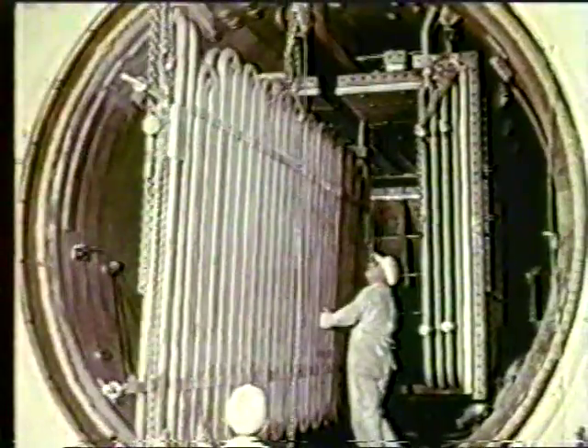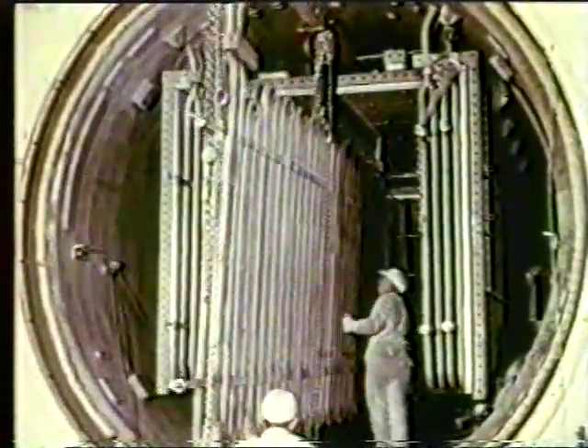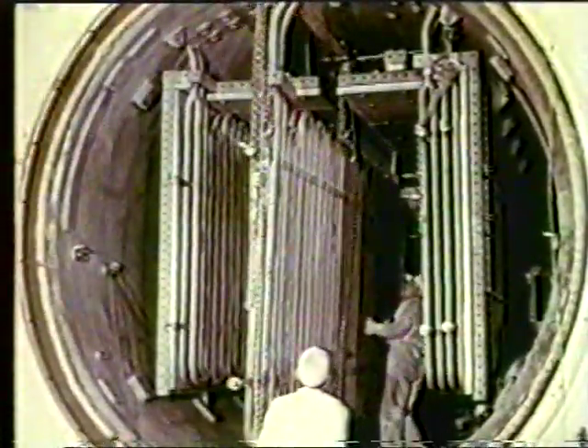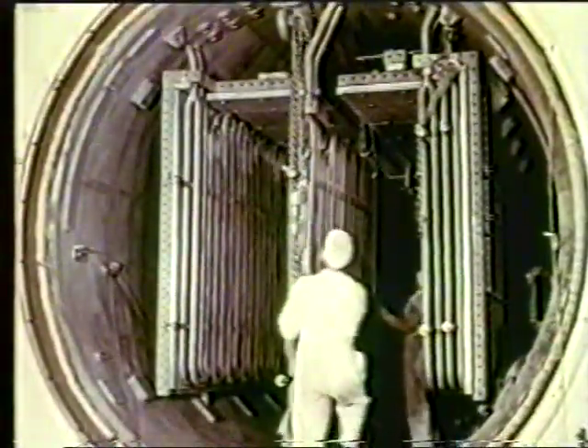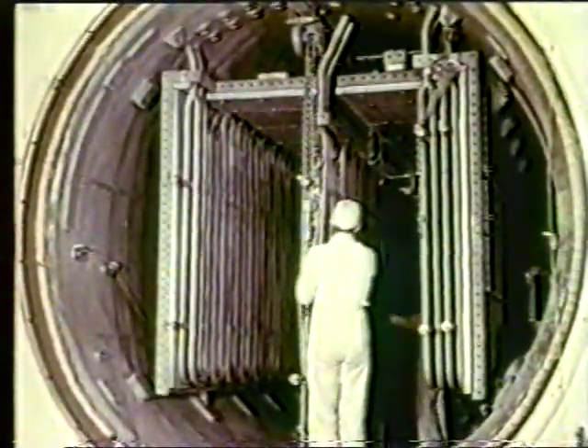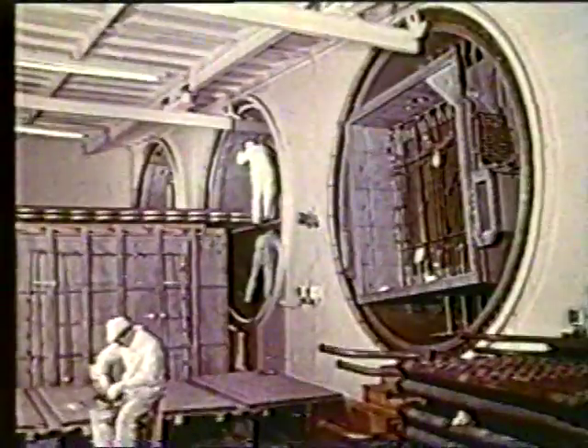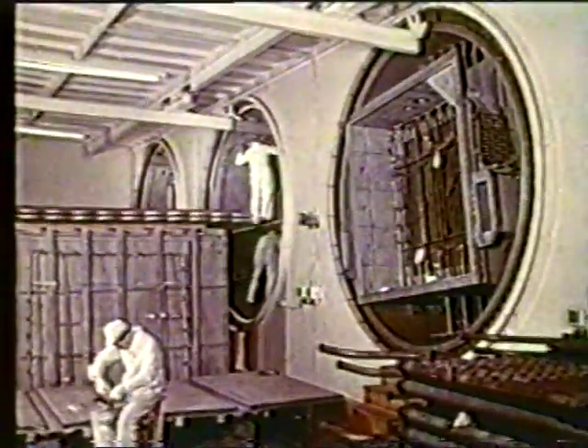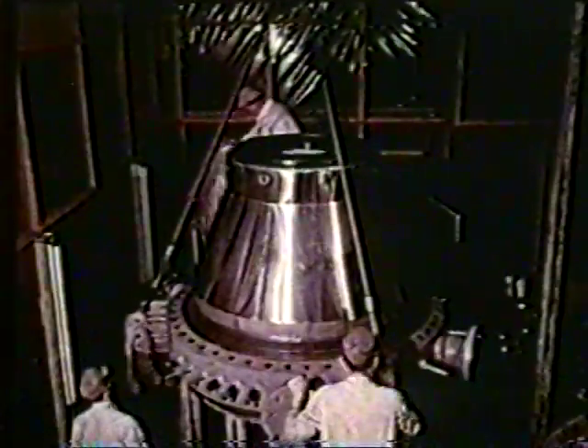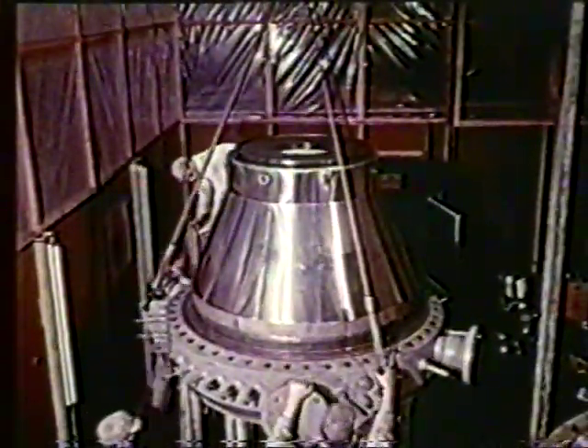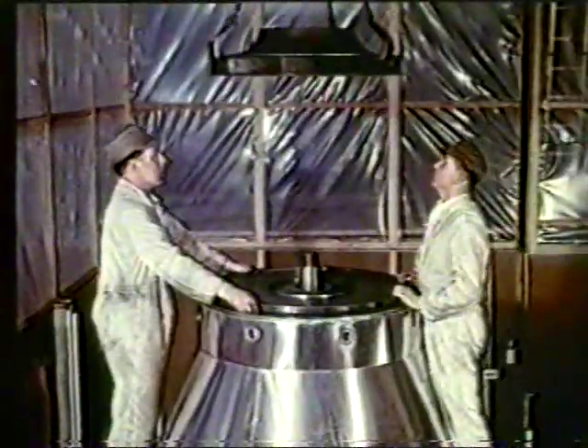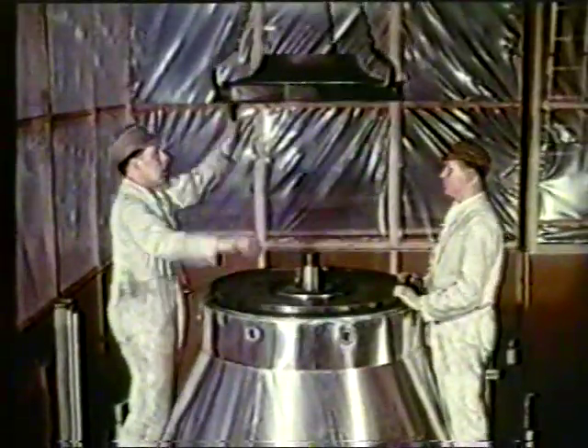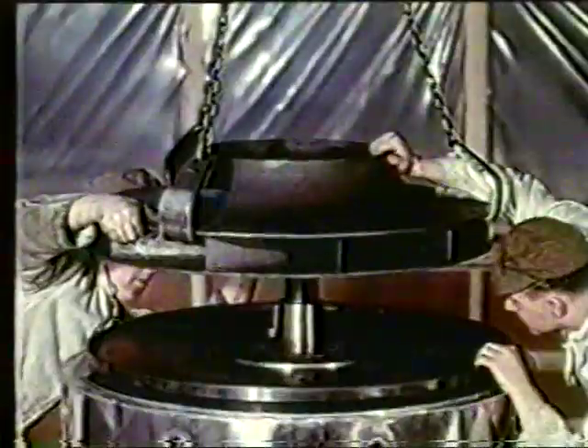The tubes are enclosed in an insulated box so that the hot gas flows up over the tubes and, when cool, returns down the sides of the vessel, thus minimizing the temperature to which the pressure shell is exposed. Another novel feature of the design was to set the circulator in the base of the heat exchanger, from which the cool gas is returned to the reactor through the annulus of the duct.